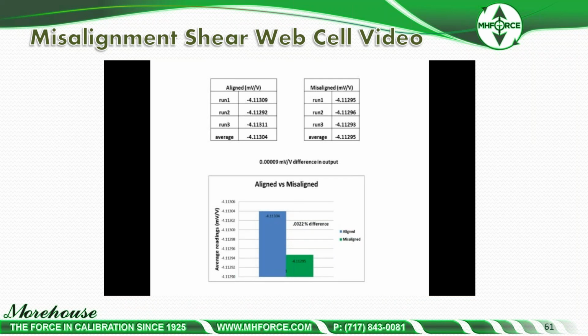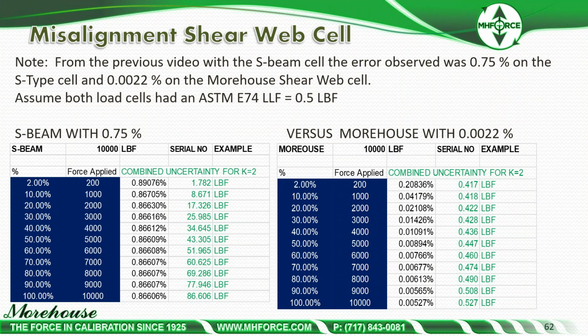I mean, aligned versus the difference: only 9 counts at the 5th decimal place. That is a 22 part per million error. That is not high at all, and that is really deliberate misalignment of the load cell. Those that were there last week probably saw the S-beam, and when we do the same thing with an S-beam, but only slightly misaligned, we show a 0.75% error versus 22 parts per million. What that effectively does on the S-beam is raise the uncertainty by a factor of 10. On this type of load cell, it raises the uncertainty by a factor of like 0.2. So 10 times versus 0.2.